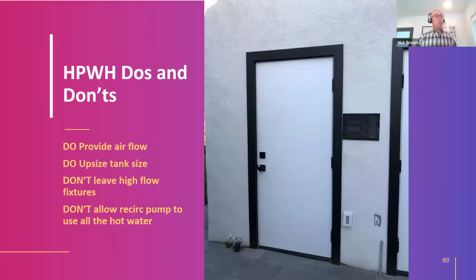Starting with airflow—remember, heat pump water heaters take their heat from the air around them. If you only give a small amount of air to the closet, like shown here, the heat pump water heater doesn't have enough heat to do its job. They pull heat out of the air they suck in through their fan and spit out cold air once the heat's been removed. So we're creating a refrigerator in this closet with insufficient ventilation, and now your heat pump water heater will be sucking in cold air—it won't be efficient. This should be a fully louvered door for the heat pump water heater to work right.